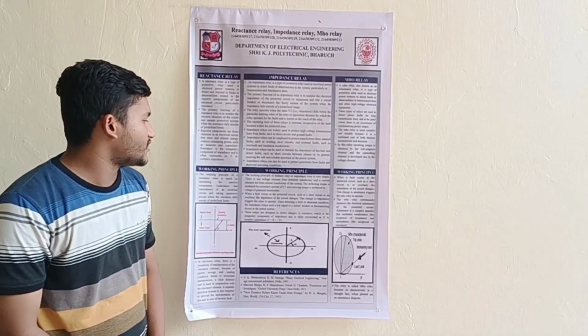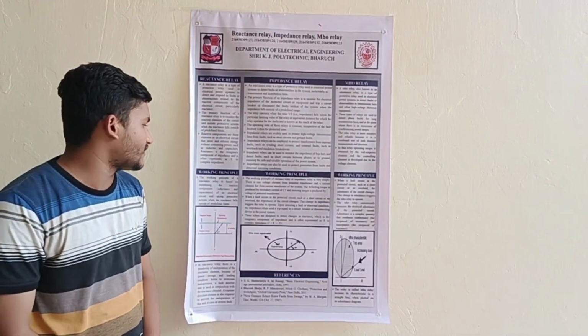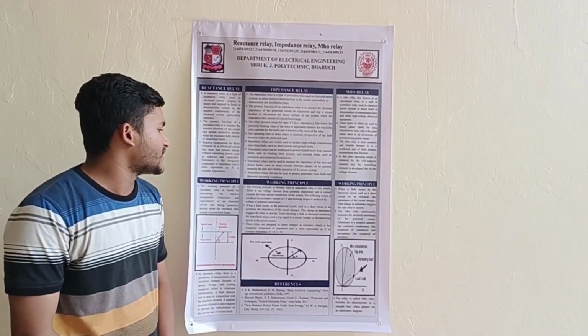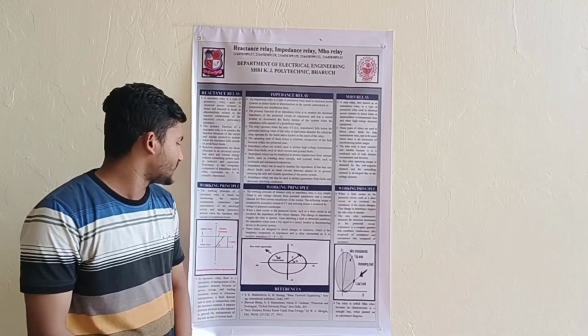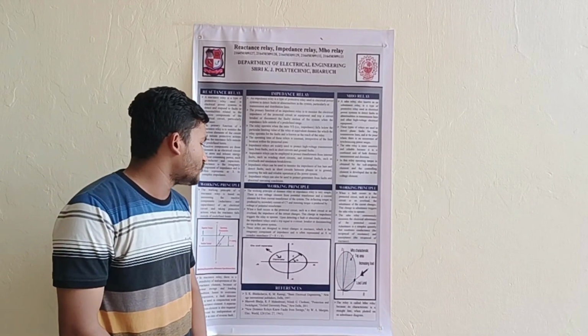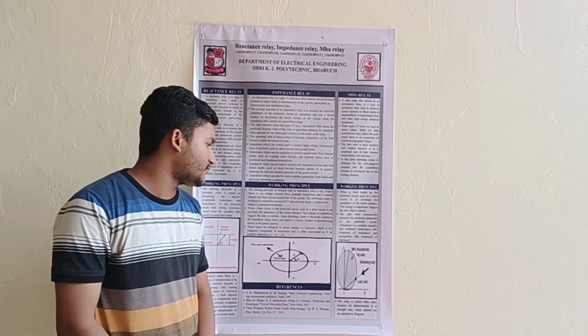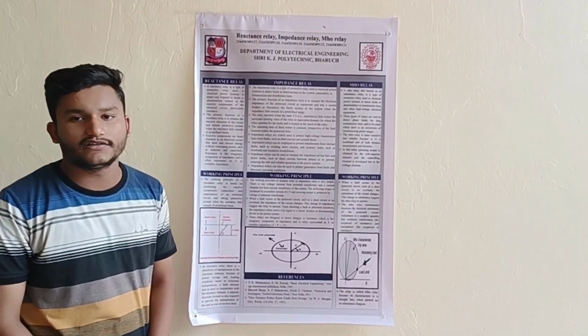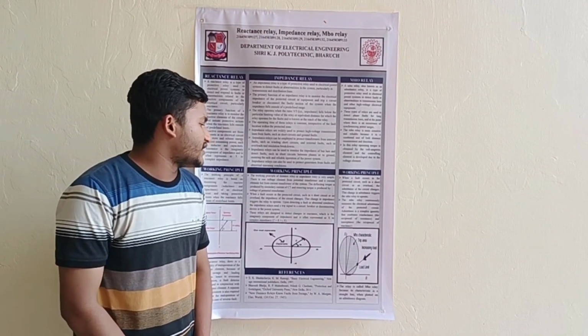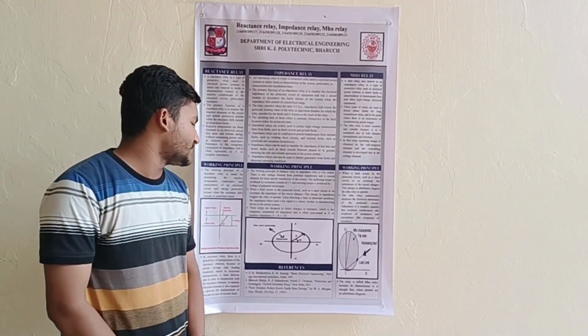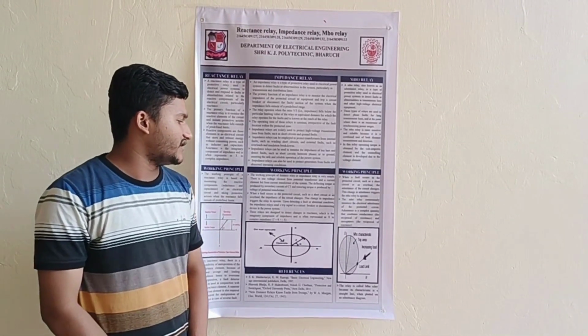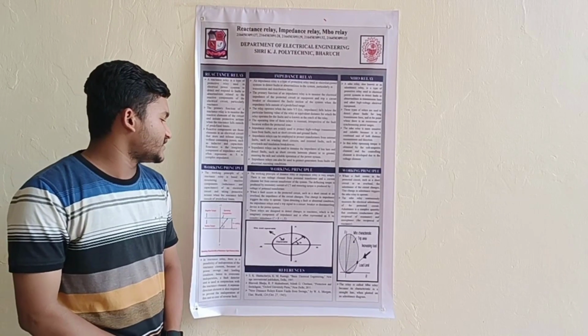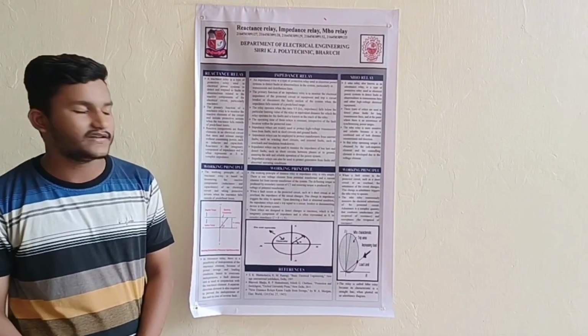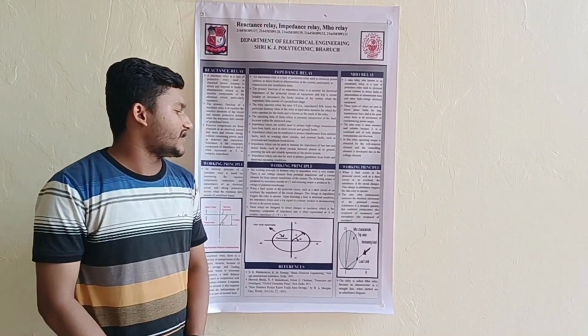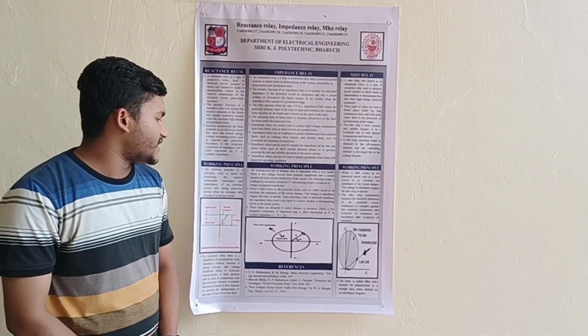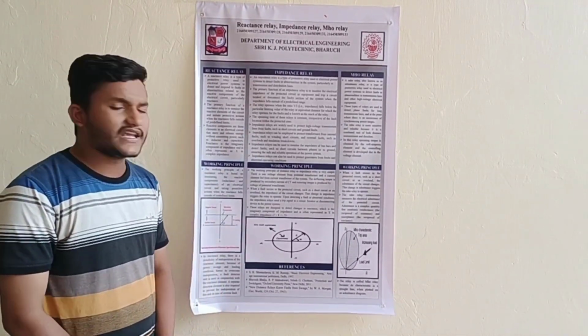A fault occurs in the protected circuit such as a short circuit or an overload. The impedance of the circuit changes. This change in impedance triggers the relay to operate upon detecting a fault or abnormal condition. The impedance relay sends a trip signal to a circuit breaker and disconnecting device in the power system. These relays are designed to detect change in reactance, which is the imaginary component of impedance, and is often represented as X in complex impedance. Z is equal to R plus jX.